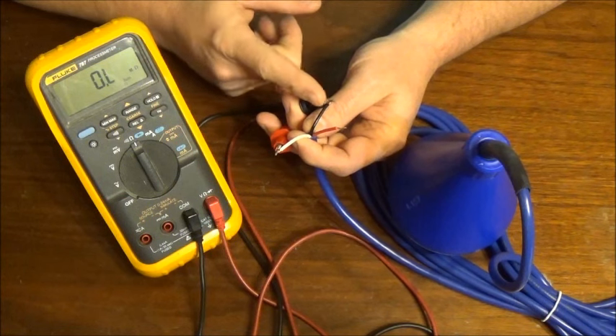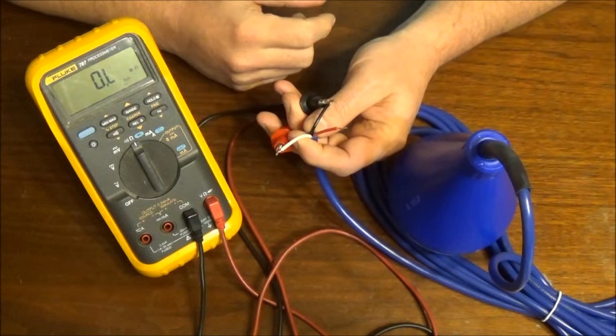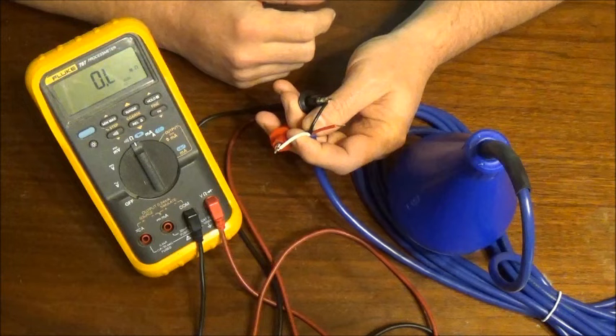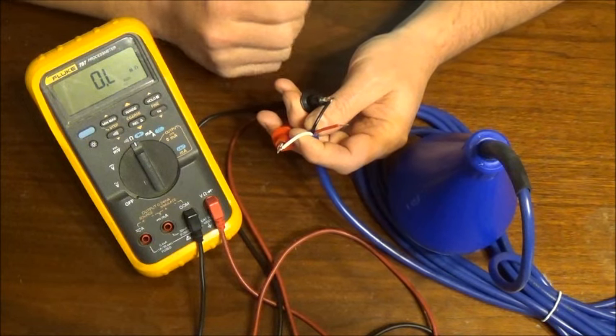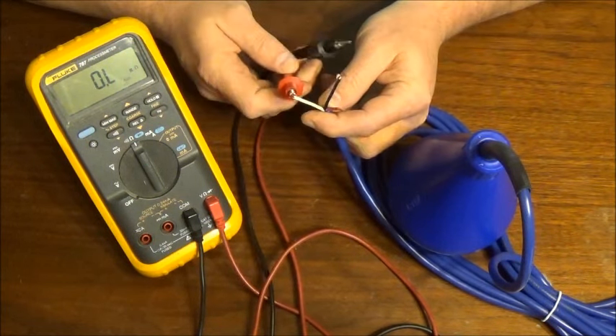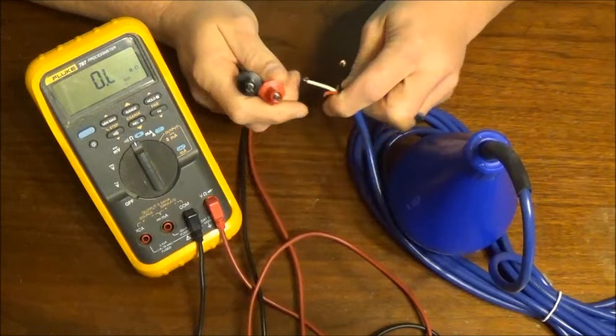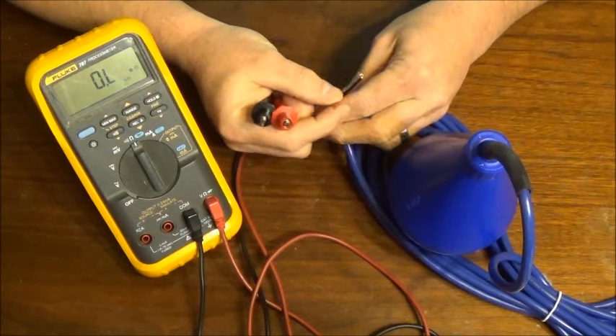I measured intentionally across the two output conductors of this float switch, one lead being normally open and the other being normally closed. Now I'll show you how it should read and operate, moving to this red conductor on this float.